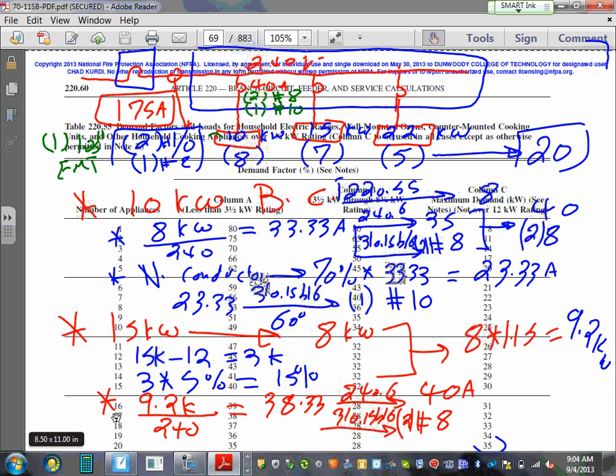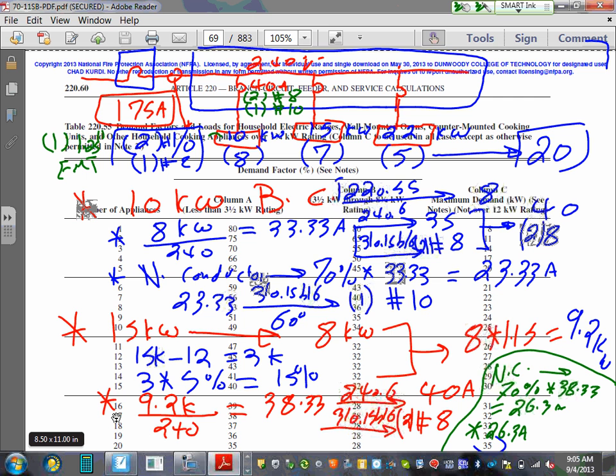Now let's do the neutral. I'm going to make myself a little bit of room here. For the neutral conductor, what you're going to take is 70%. Do me a favor, 70% multiplied by 38.33. Can somebody give me the math for this, please? 26.3 amps. And then for 26.3 amps, that will give you one conductor number 10. So my neutral is number 10, one conductor number 10. Which table? 310.15 B16.